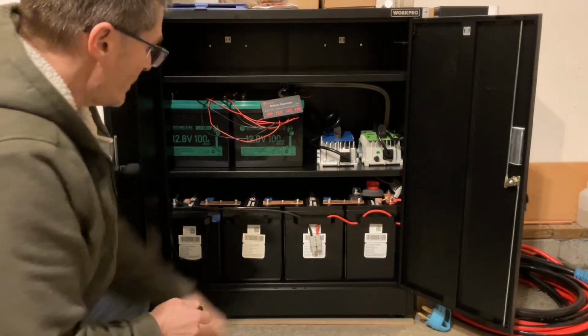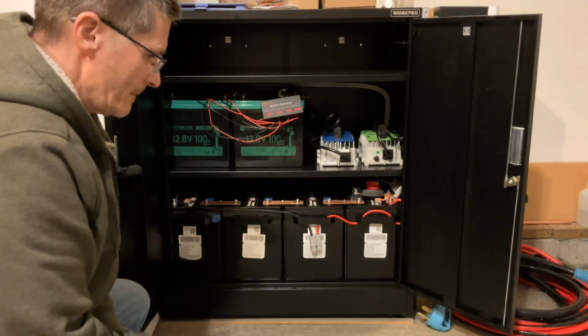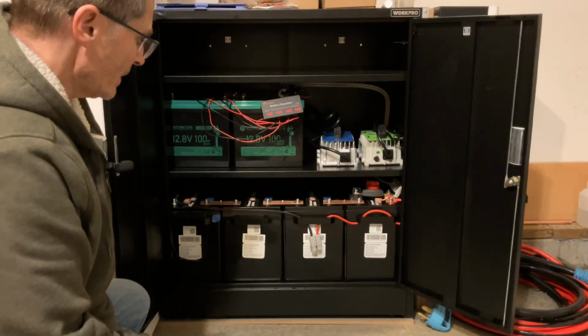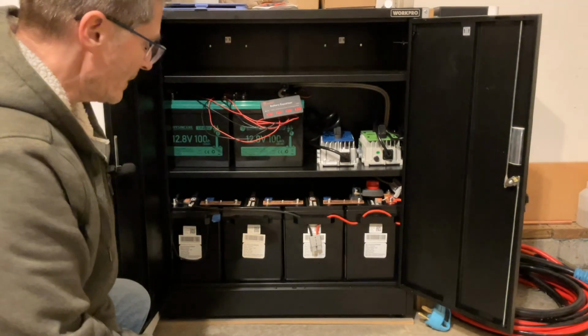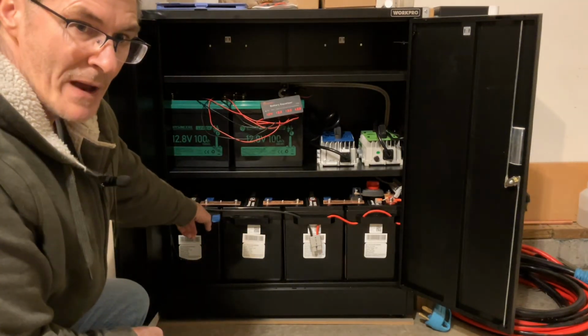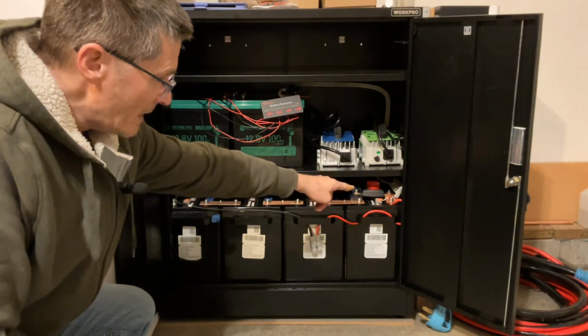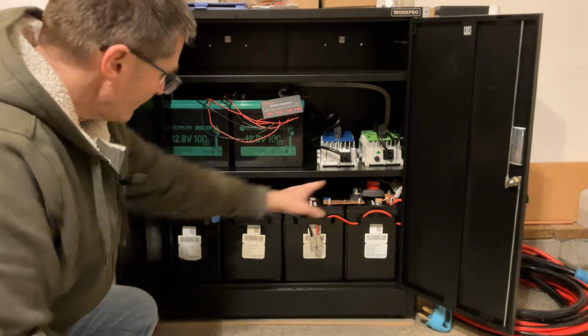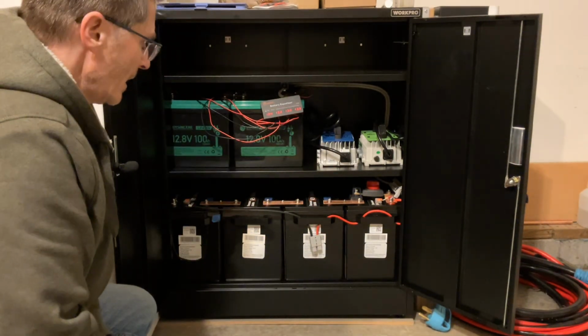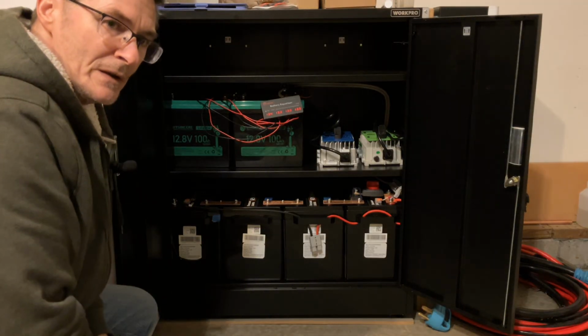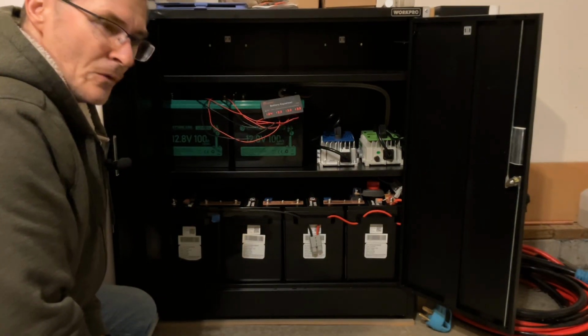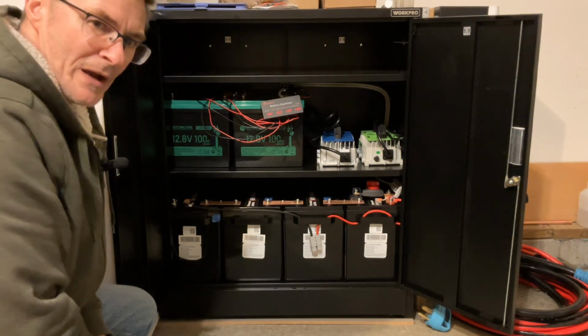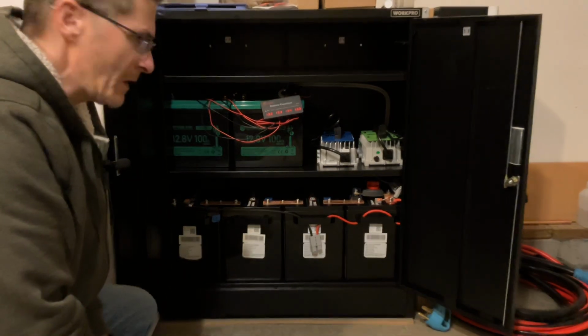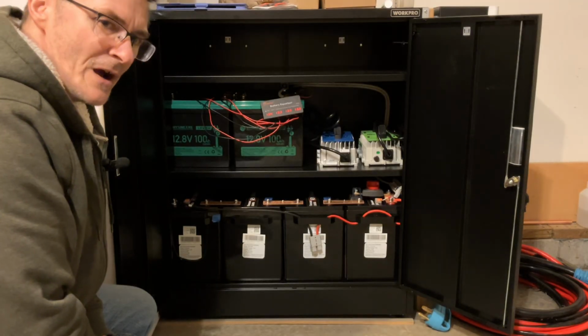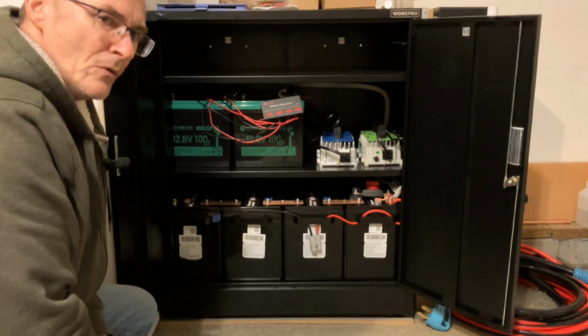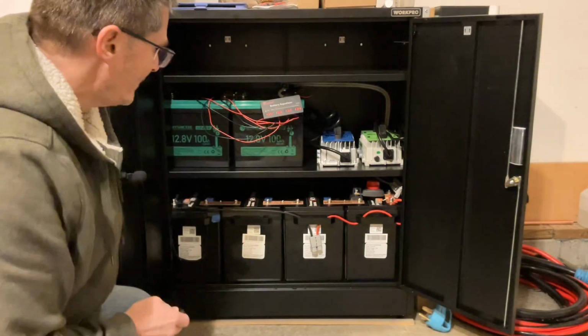The bus bars on the bottom of the cabinet, I'm not so concerned with. I'm going to just fabricate some covers to go over each one of those. The main negative of the battery pack is on the left side, and the main positive on the right side. It gives a good distance across those two terminals that would inherently prevent small tools, or just under normal maintenance, your hand coming in contact across both of those posts and potentially presenting a shock hazard or a short circuit with your tool reaching across the 48-volt battery bank.